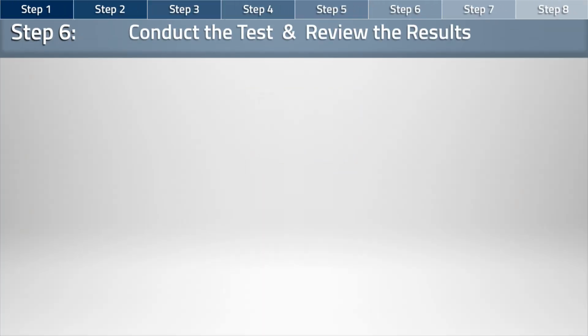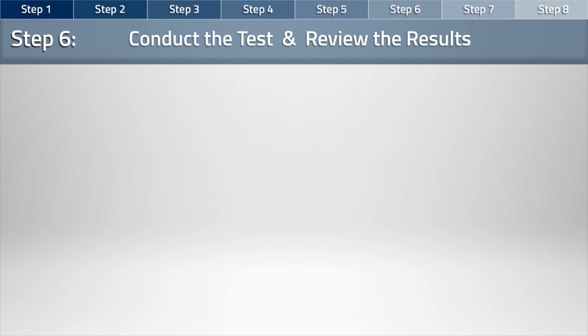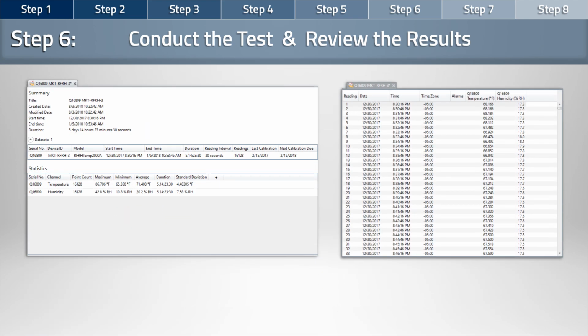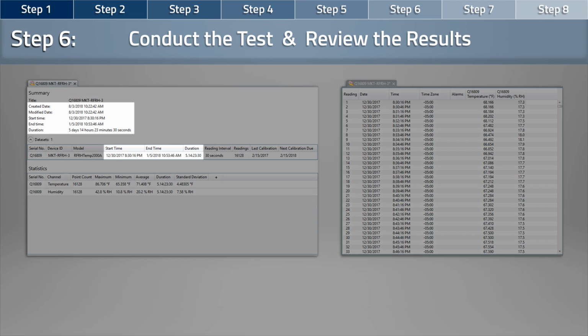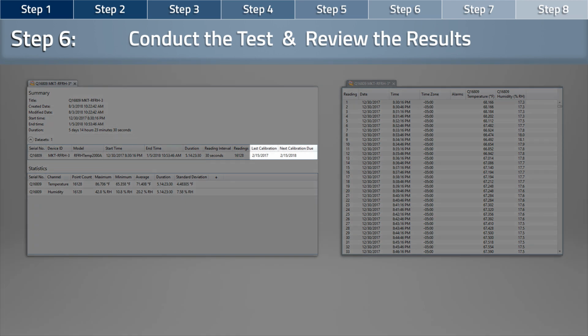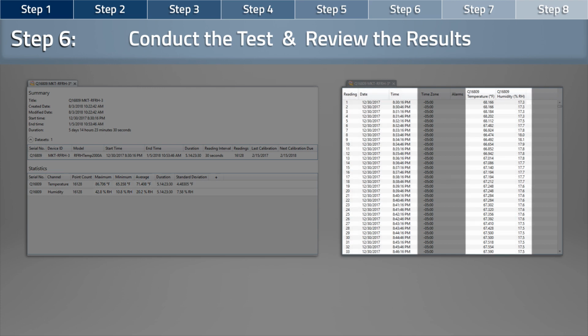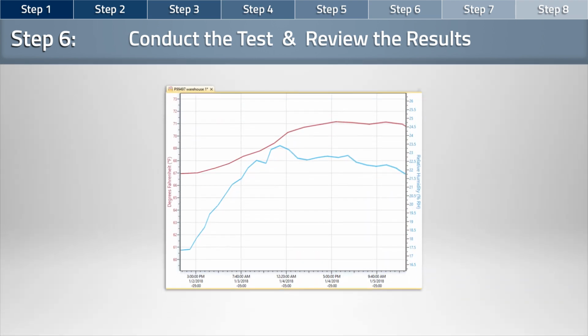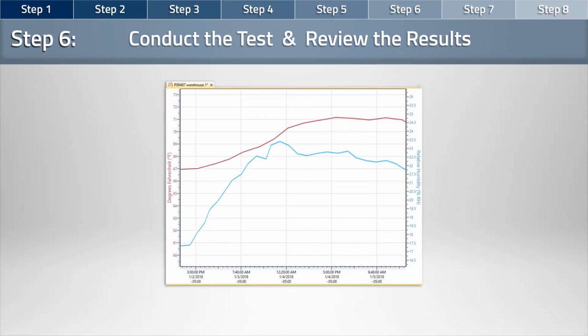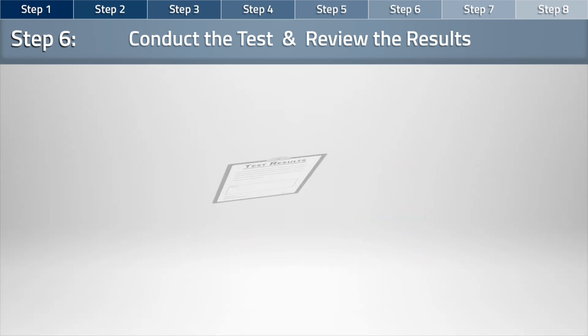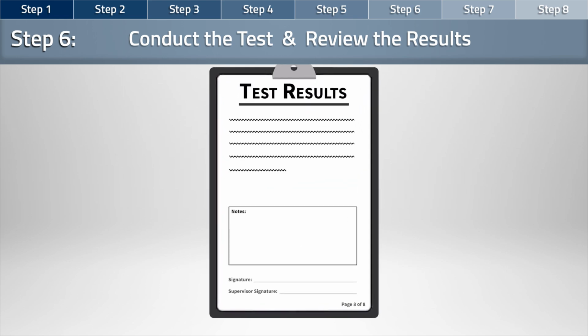It's now time to conduct the first test and review the results. The important information collected from the test will include the date and time of the study conducted, calibration information of all equipment, the reading rate used, minimum, maximum, and average statistics for each channel, timestamps for each reading from each logger, and a graph display of all data recorded during the test. You should also provide a space for notes and signatures on this test results document.